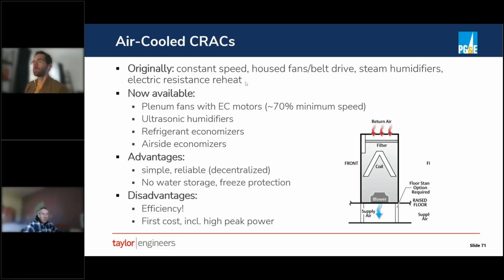By comparison, a good PUE today is like 1.1, which means the mechanical system is only using about 10% of the power of your computer. We've come a long way. And even with CRAC units, we've come a long way. You can now get CRAC units with plenum fans instead of housed fans.